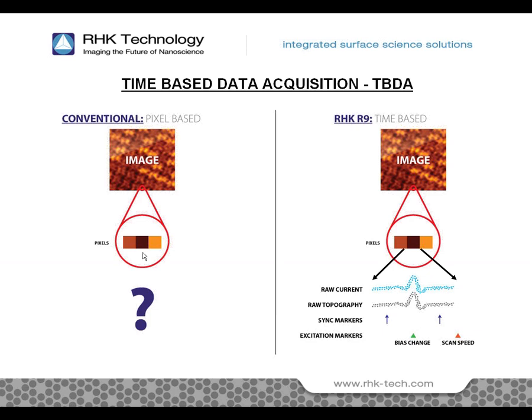Changes to parameters are also kept during the measurement, so you'll always know exactly where and when the parameters changed. In the example on the right, the R9 will display that the bias voltage has changed at that pixel location and that the current and topographic signals spiked in response.